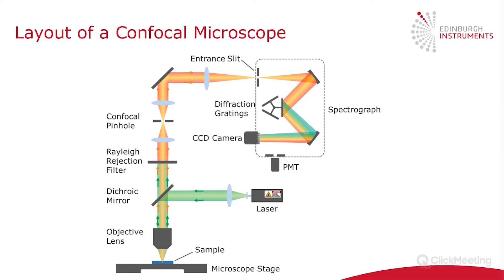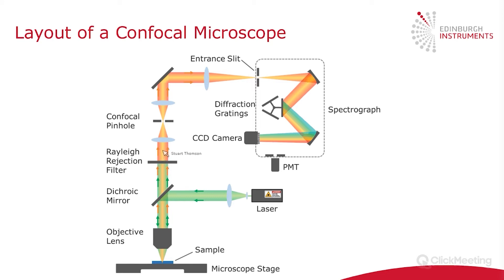This excitation either creates photoluminescence or Raman, depending on what you want to look at, which is then reflected from the sample and collected by the objective lens. So it's a reflection configuration, also known as an epi configuration. This photoluminescence or Raman then passes up through the dichroic mirror and is then filtered through a rejection filter, which removes all the excitation wavelength that might have reached this point.